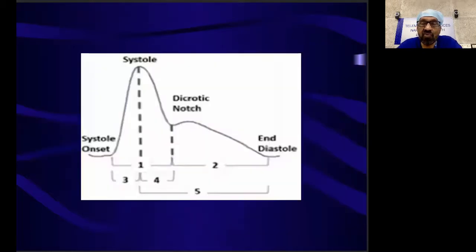This is dependent upon the arterial pressure tracing waveform, and this software depends upon the 5 parameters which are depicted here: the systolic phase of the arterial pressure, the diastolic phase of the arterial pressure, the systolic rise phase, the systolic decay phase of the arterial systole, and the overall decay phase.